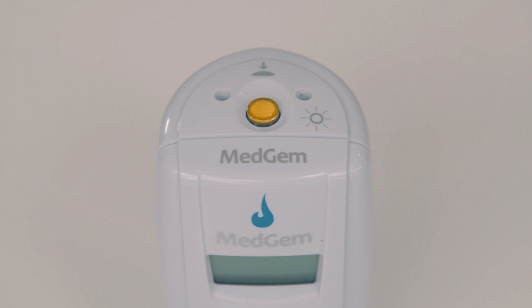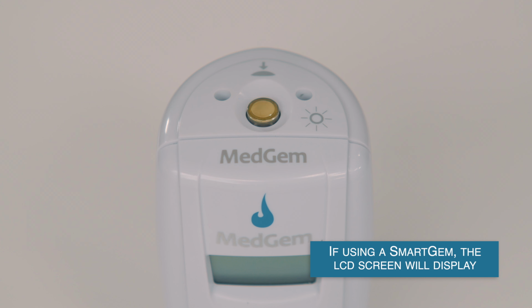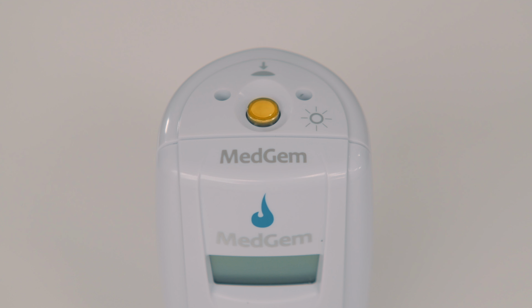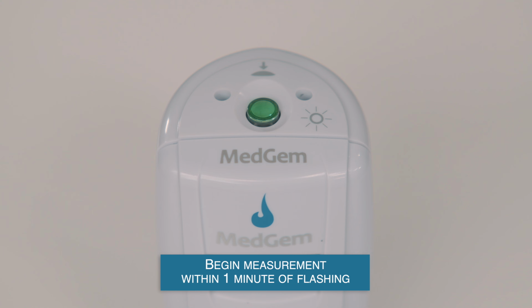Power on the device and see the amber indicator light begin to flash and the MedGem device buzz softly, indicating self-calibration has begun. This typically takes up to 30 seconds. When the MedGem device is ready to begin a measurement, the indicator light will flash green and the MedGem device will beep once. Begin the measurement within 1 minute from the time the indicator light begins flashing green.